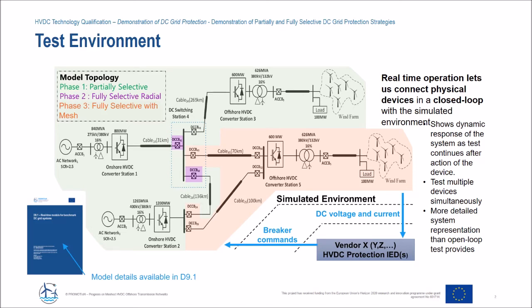For us, the AC networks were modeled in the so-called large time step, with a similar 50 microsecond time step that was used at SuperGrid. But for us, with the partially and fully selective schemes, because they're that bit quicker, the full DC network, including the converters, was all modeled in the small time step. So that was about a 4 microsecond time step we used in there, with full frequency dependent cable models used, so that we could see the fast approaching waveforms that the IEDs would be expecting to see in real life.